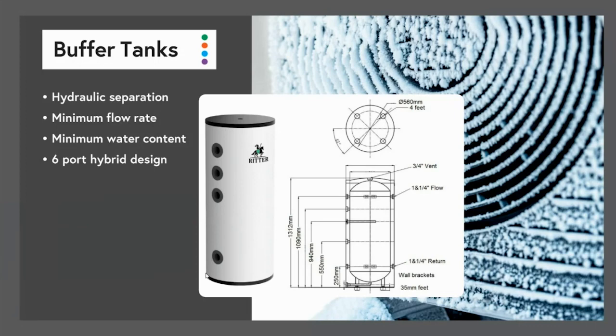So obviously when it needs that energy, that amount of water, which in most heat pumps is somewhere between 20 and 40 litres, it needs it stored to be able to do the defrosting cycle. Obviously, the bigger the heat pump, the more water that it needs. Now, this tank here is 100 litres. The reason it's 100 litres is because it's a hybrid tank, and the reason I brought this up is because this tank allows a boiler and a heat pump to be connected together.